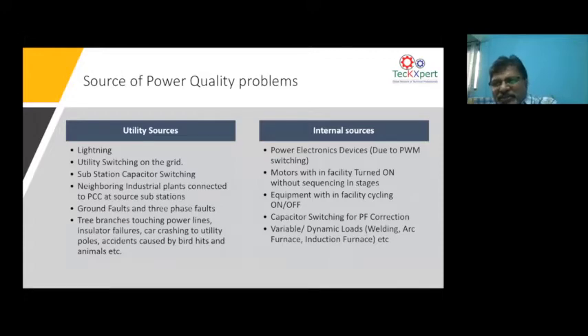Similarly, capacitor bank switching inside the facility can also cause internally generated power quality problems. If we look into automotive plants or a steel plant, where they have arc furnaces or welding loads, all those dynamic variable loads also create power quality problems. So that means sources of power quality problems are at the utility, which is your utility supplier, and also internal sources. So the PQ problems are caused by the consumer as well as the power provider. That's right.